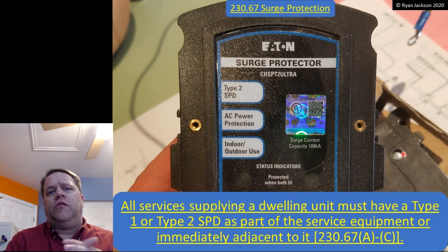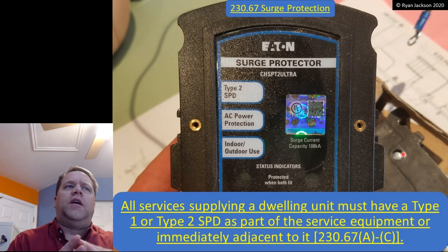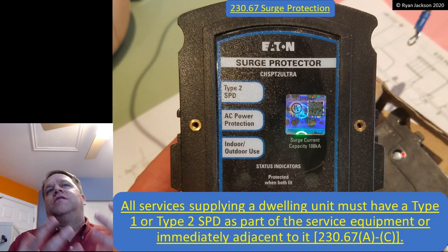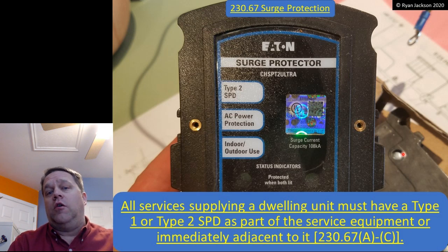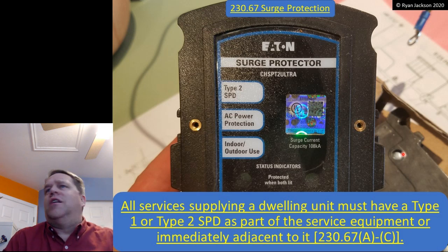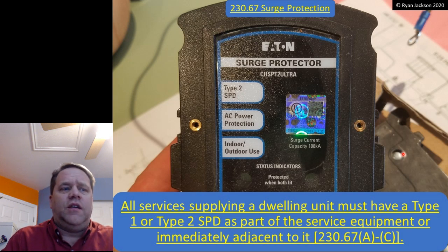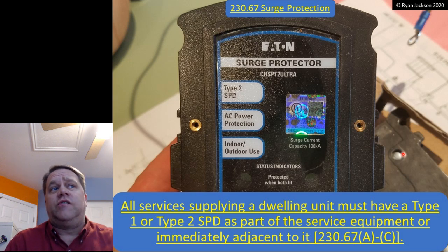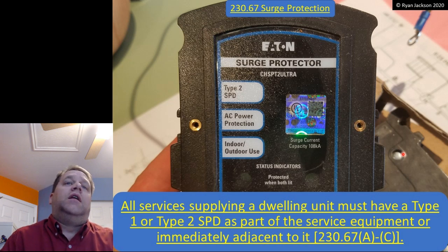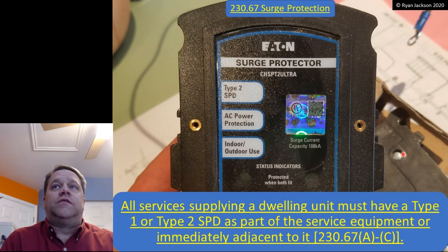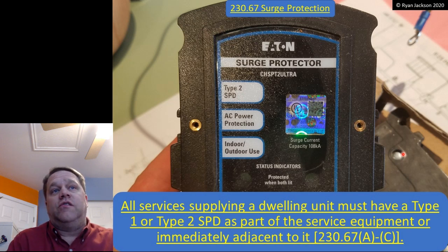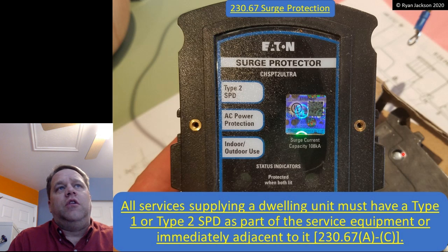The reason this was put into the code is, according to the code making panel, we depend on sensitive electronic equipment a lot more in our homes today than ever before. And it's not just our TVs and computers. It's our smoke alarms, AFCI circuit breakers, GFCI circuit breakers. These things have sensitive electronic components. And one surge from a utility or maybe a lightning event shouldn't wipe out the smoke alarms in our house. So to prevent that from happening, we have this new rule 230.67, which requires a surge protective device.